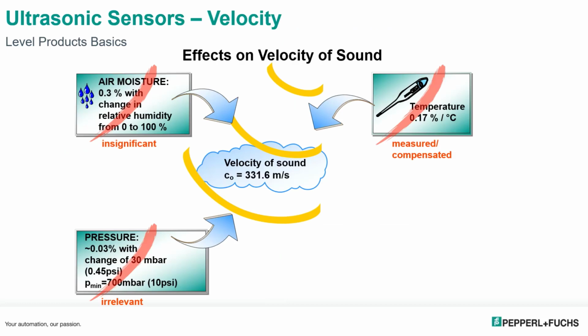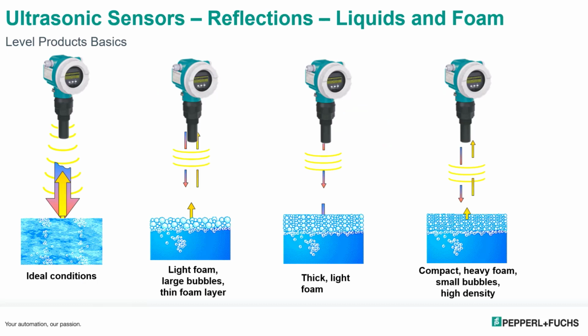Now, the ultrasonic, again, uses sound waves to send and receive its signal. Because it's a very robust signal, air moisture and pressure are irrelevant to the signal coming back as far as the speed. Temperature can cause fluctuations in the speed of sound. However, we do compensation inside there, so even temperature changes are compensated out to give you an accurate signal and accurate level. Now, when you're looking at the medium it's bouncing off, you have to consider the actual surface of the medium.